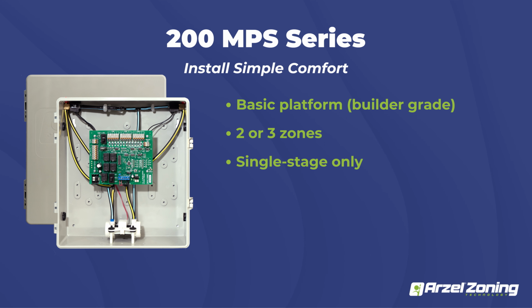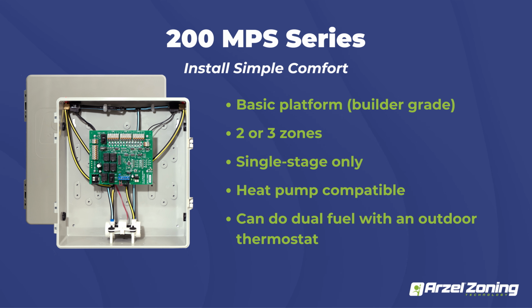So if you guys are doing multi-stage equipment, or if you have a customer with an older piece of equipment that they're probably going to end up replacing in the next couple of years with 2-stage, you're probably going to want to steer away from this panel and go with something like our HeatPumPro or an AirBoss. But it does work for heat pump, single stage, or conventional equipment. Not really great for dual fuel. We can make it work, but we have better panels out there that'll handle dual fuel capabilities a lot better than this panel. So just keep that in mind.